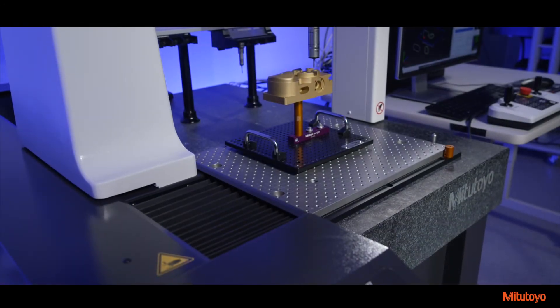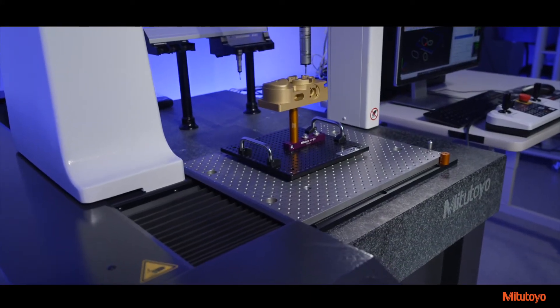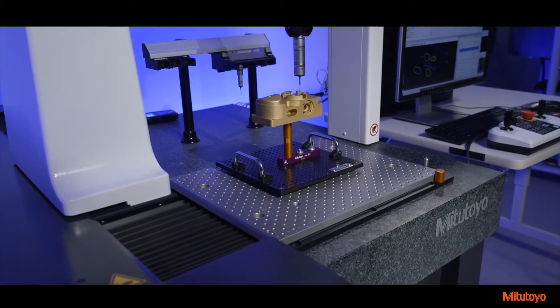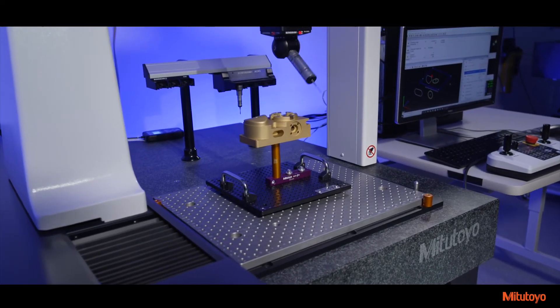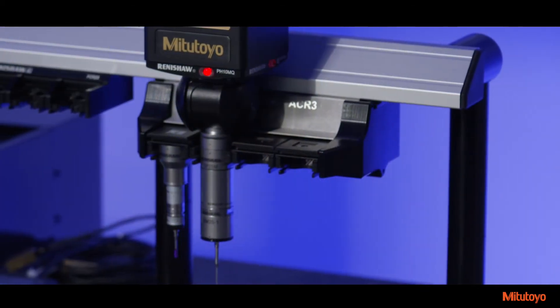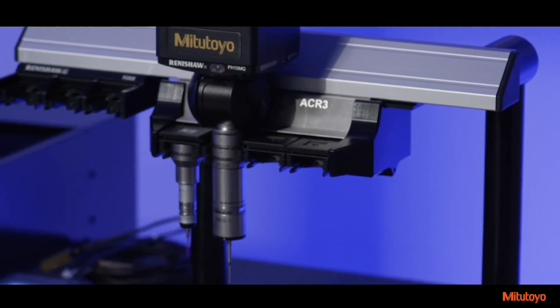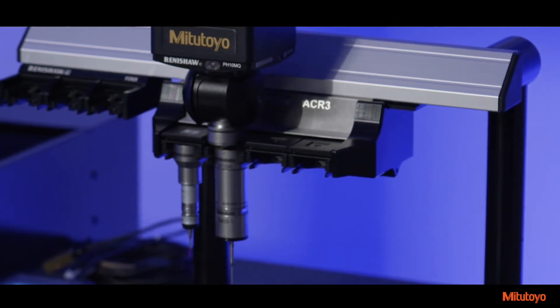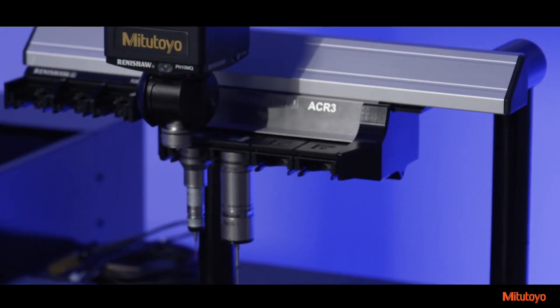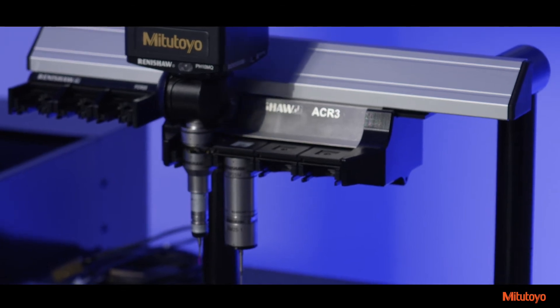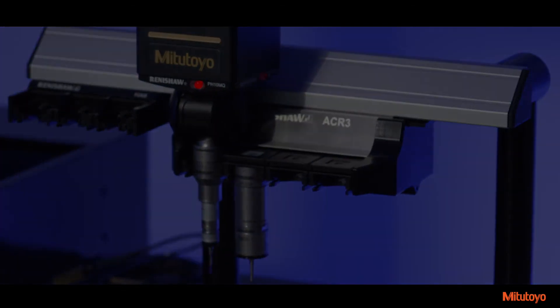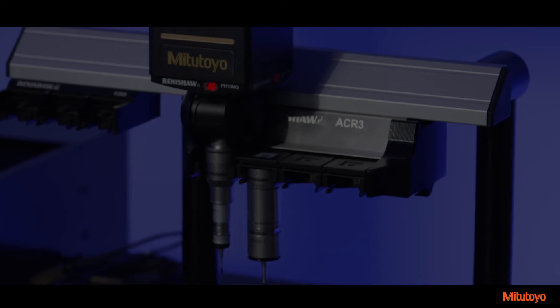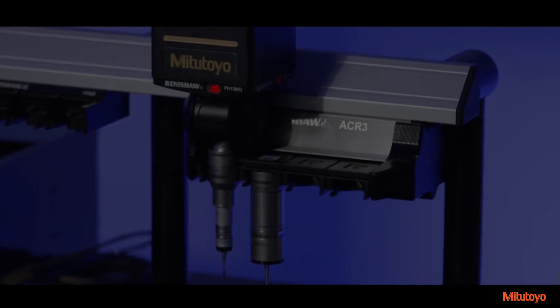Users will be able to choose the optimal probe for their workpiece from Mitutoyo's lineup of CMM scanning and non-contact probes. By consolidating and eliminating previous models, the PH10MQ probe is the standard configuration. This makes serviceability and support easier. Additionally, support is offered for shank-mount probe configurations, but require additional hardware.